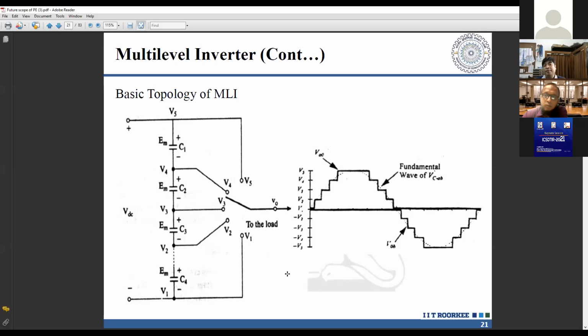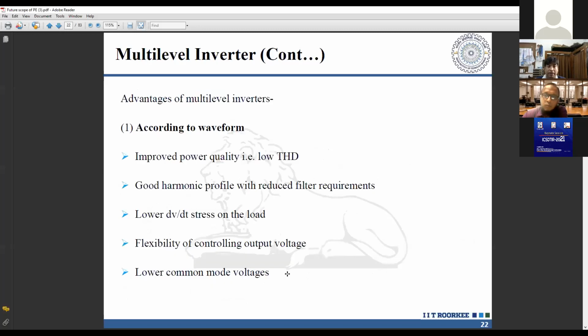All those can be tackled by the multi-level inverter. So in brief, what we can say is that it improves the power quality. Why? Because it suppresses the number of harmonics, gives a good harmonic profile, and the requirement of the filters is reduced. If you use the square wave, then we have to put in the filters. Ultimately, the filter takes the brunt of the harmonics problem, and thus the lifetime of the filter will be less. Ultimately, we require to replace it after a few years. Therefore, it leads to lower dv/dt and losses.